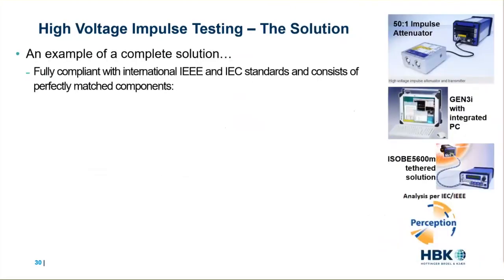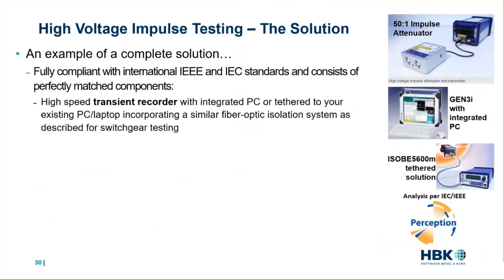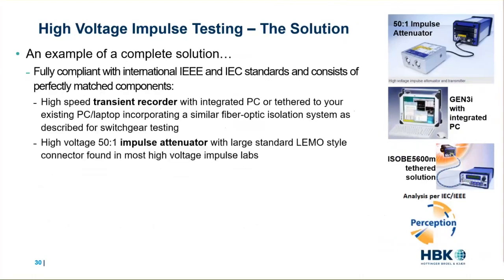Here's an example of a complete solution which is fully compliant with the IEEE and IEC standards and consists of perfectly matched components. You've got a high-speed transient recorder with an integrated PC or tethered to your existing PC or laptop, incorporating a similar fiber optic isolation system as we described back during the switchgear testing application. You also have a high voltage 50-to-1 impulse attenuator, which has a large standardized LEMO style connector, which is found in most high voltage impulse labs.